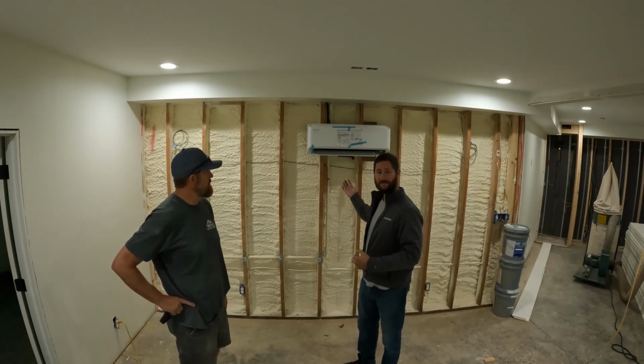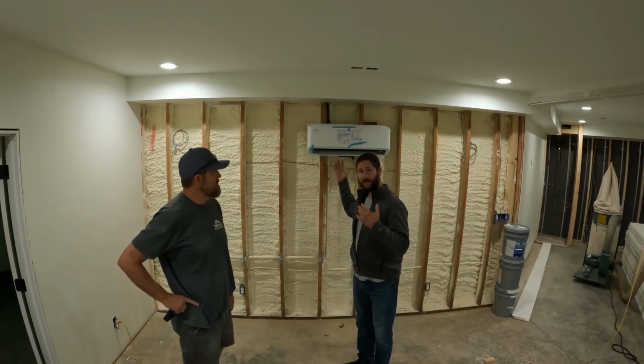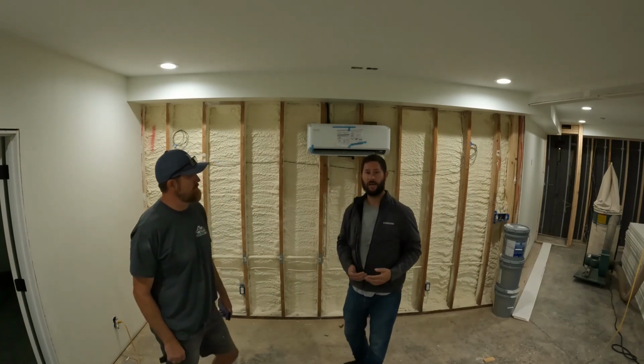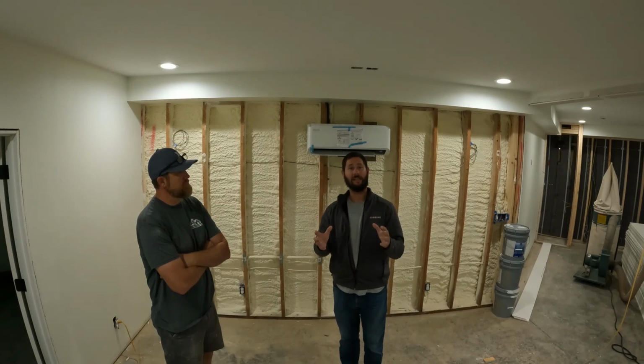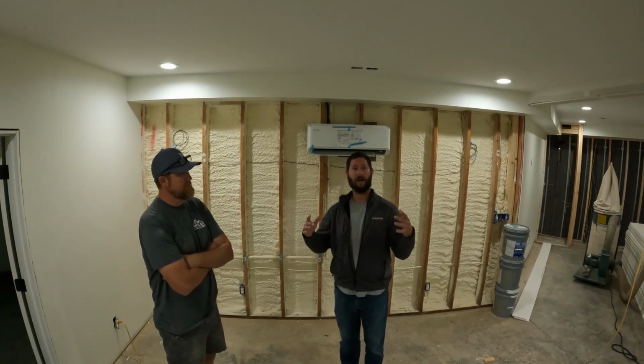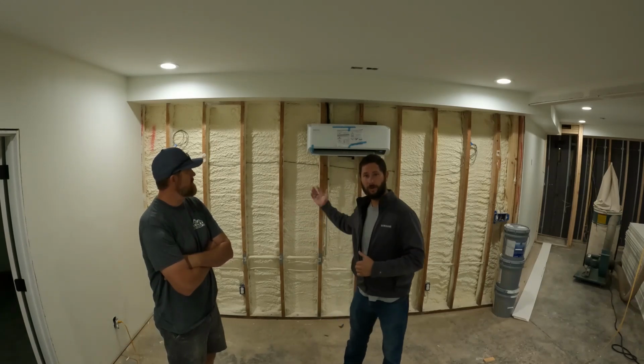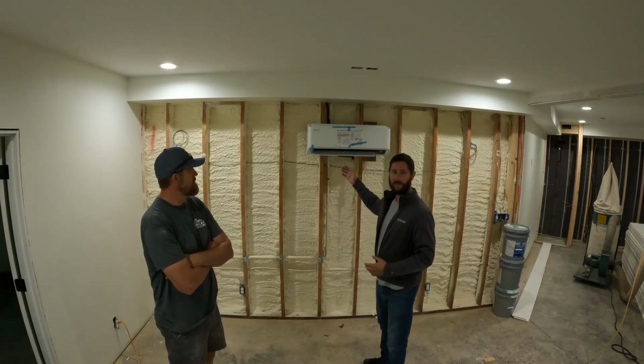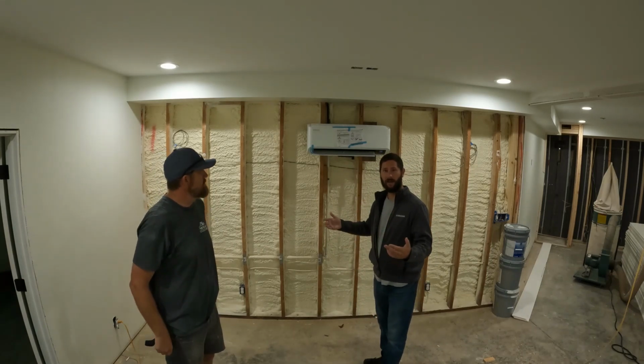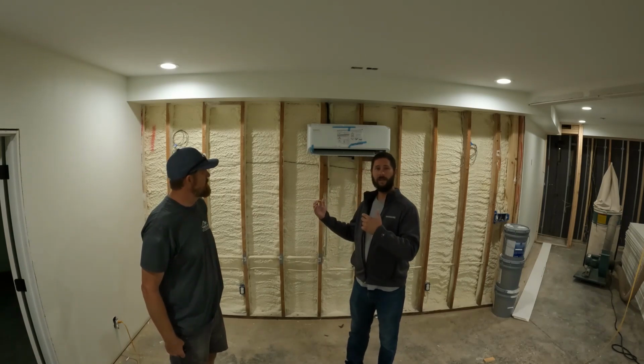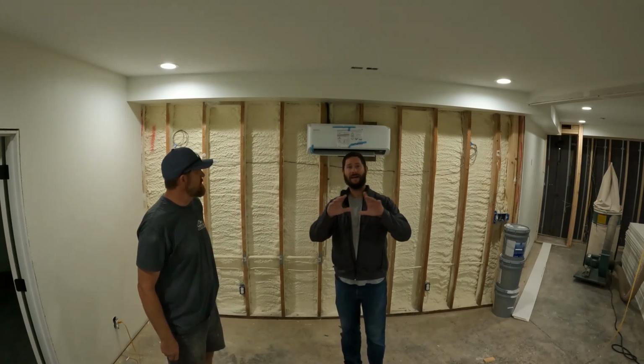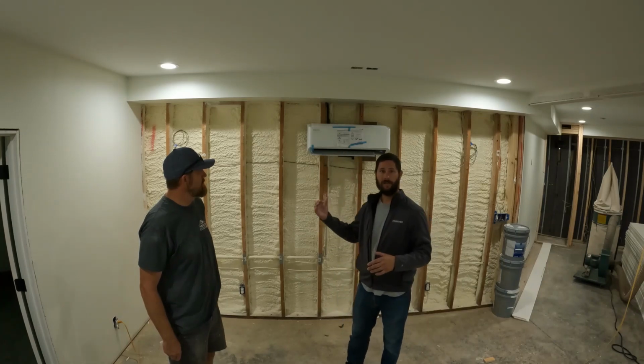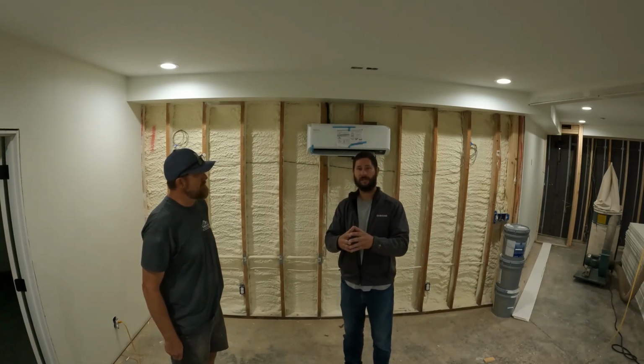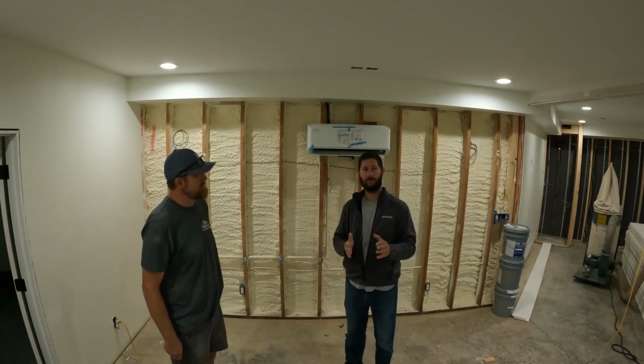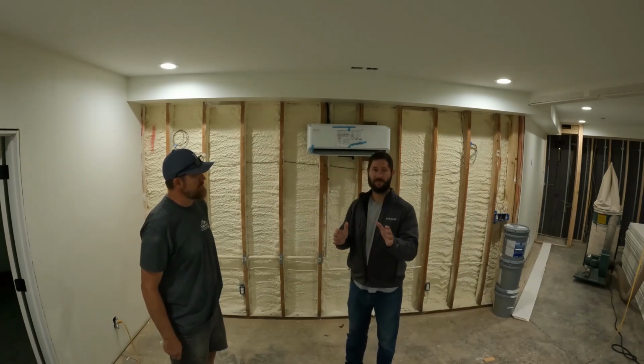As far as mini splits, they're great because you can oversize this equipment and it's still not oversized for the home. Foam houses are tight like an envelope, so there's not a lot of infiltration. There's not a lot of thermal loss to the outside when there's 95-degree days. So having equipment that varies its capacity, having equipment that has an indoor fan that runs most of the time, providing extra airflow, this equipment is so beneficial when you have that tight envelope and you don't need equipment that is running full force 100%. So this equipment is great for foam, and you can oversize this equipment because it varies its capacity.